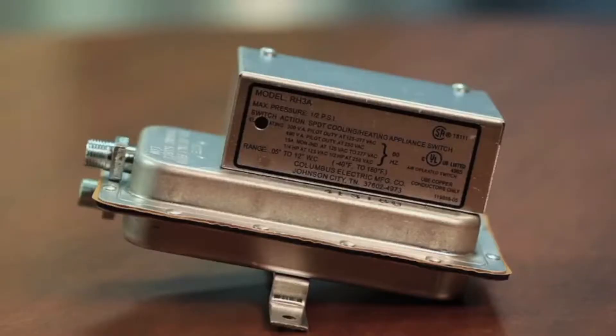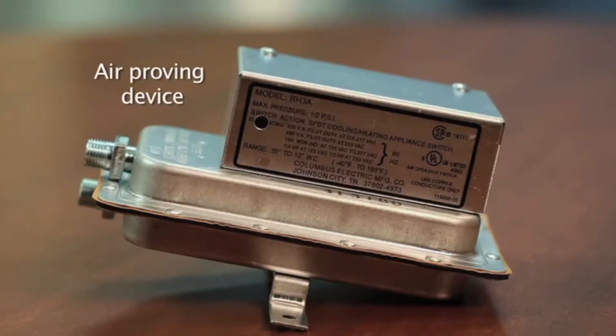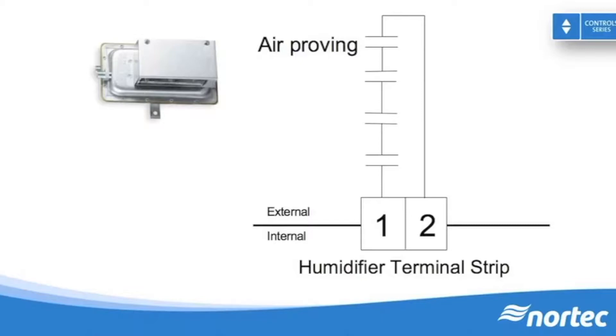Just as the name implies, the air-proving device indicates if the supply duct is provided with airflow, since we only want to provide steam to a duct that has air movement. These devices are traditionally on-off, which means they use a set of dry contacts and either close or open between the contacts. On-off devices are wired in series with each other and must complete the humidifier security loop.